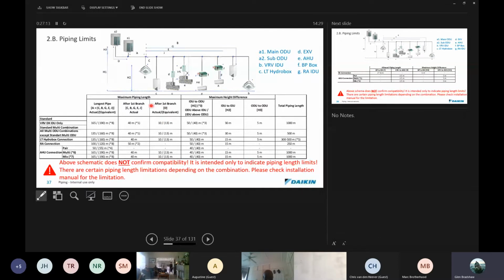Branches, for instance, between condensers, they're size D, no more than 10 meters. Between them over there. Indoor to outdoor height, we're not allowed any more than 30 meters. You'll see that if you have an LT hydrobox connection, this is reduced to 15 meters. And outdoor to outdoor height, no more than 5 meters. Total piping length up to 1,000 meters in all standard combinations, and then non-standard and all multi-outdoor combinations, except standard, 500 meters.